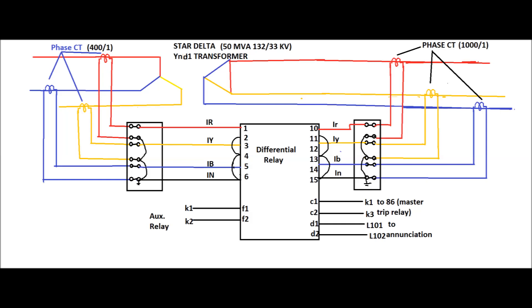The I-difference current and I-bias current are calculated. When the I-difference current is more than the I-bias current for a pre-defined value or pre-defined slope, the relay will send a trip signal by means of k1 and k3. It also sends an annunciation to operating staff by means of L101 and L102.